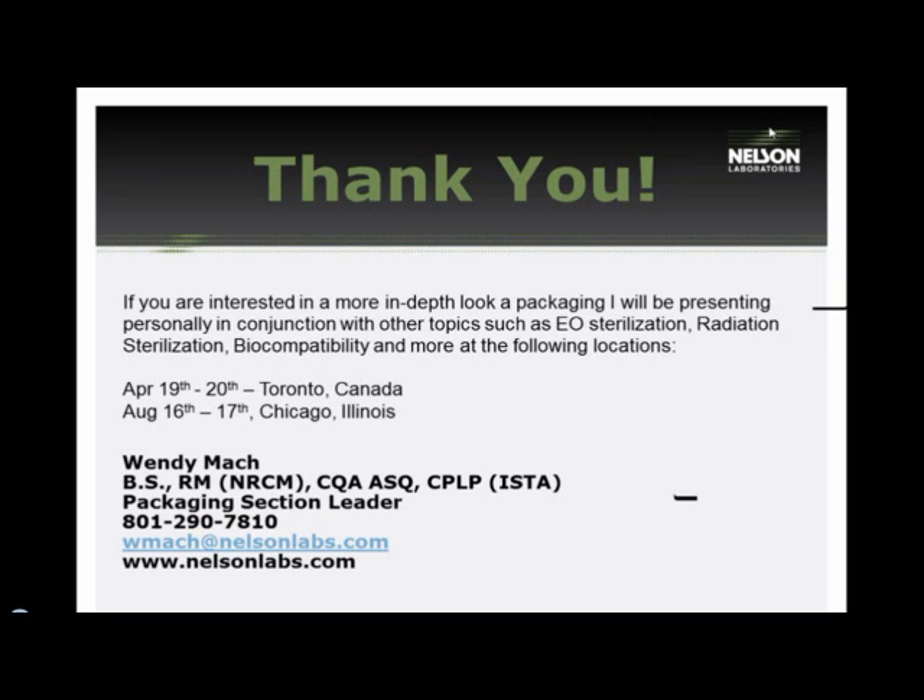Is it common to perform transportation testing for aging samples as well, or is it better to perform them separately? It depends on the purpose of the test, but the majority of the consensus is that you should evaluate climactic stressing separately. You can incorporate transportation in aging depending on the outlook you're trying to examine. Most samples do go through a transportation process and can be stored at a facility, so that would evaluate that situation.